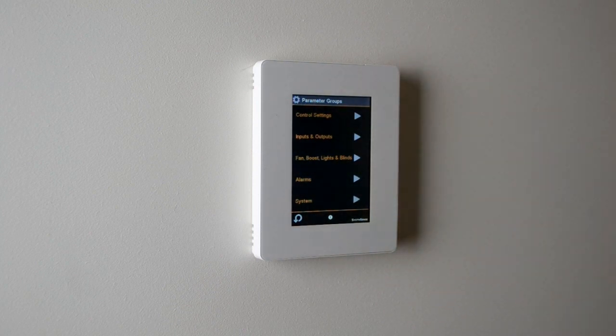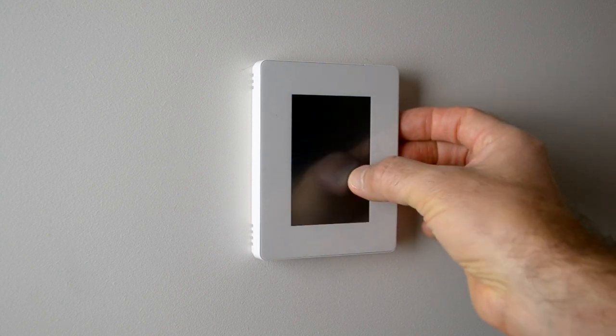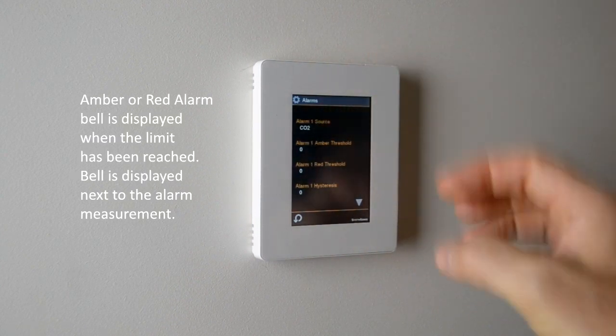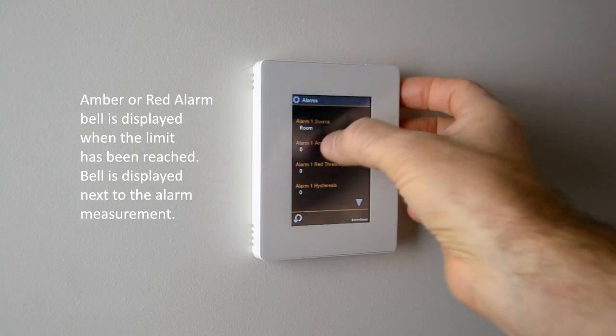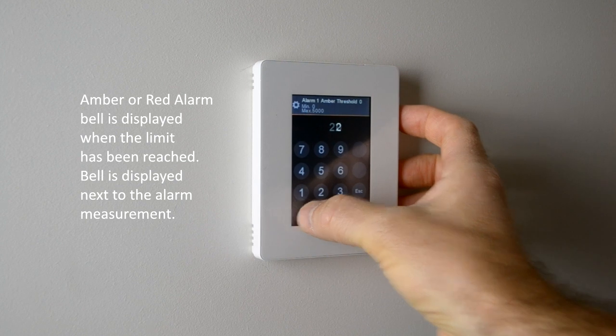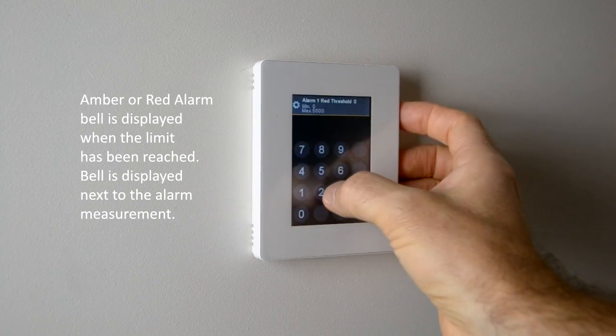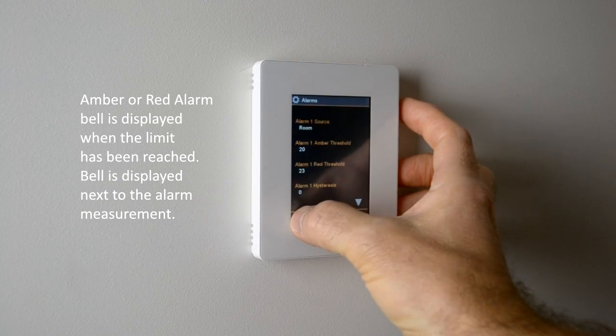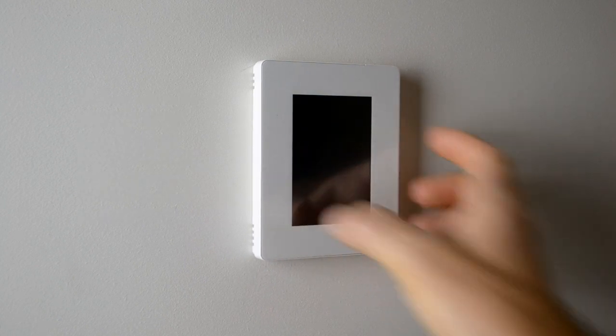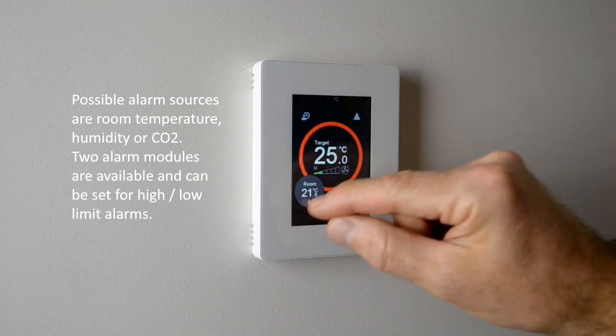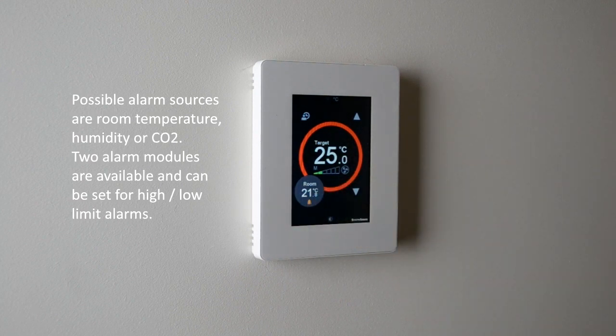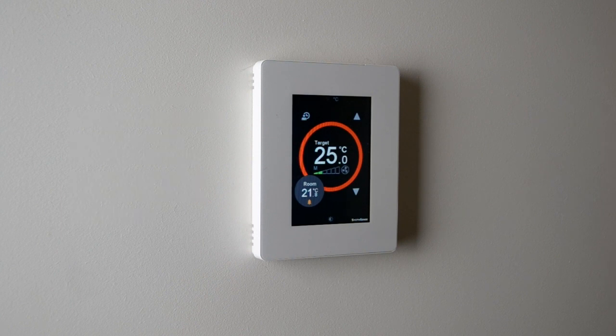We have control settings, inputs and outputs, fan, boost, lights, blinds icons, alarms, and system settings. If I, for example, go to the alarms, I can set up the alarm source. So in this case, I put the room temperature, I put the amber alarm threshold to 20 degrees, and then I put the red alarm threshold to 23 degrees. And if I now come back to the front screen, after changing the settings, you can see there's a little alarm bell icon there. So this is again another very useful function to alert the users if the temperature or CO2 or humidity goes above or below certain values.